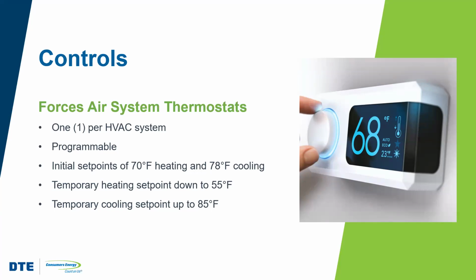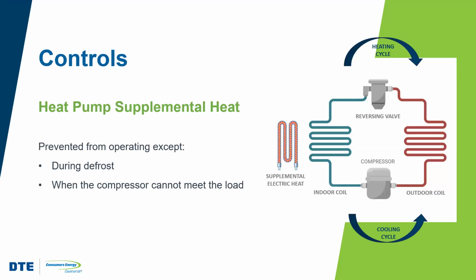The interior design conditions for a good design are 72 degrees Fahrenheit for heating and 75 degrees for cooling. But to encourage reduced energy use, the initial thermostat set points at turnover should be 70 degrees for heating and 78 degrees for cooling. And if the system includes a heat pump that has supplemental electric heat, the controls should ensure that that electric heat only comes on when the compressor system is not able to provide enough heat to meet the demand. And this can be located in the thermostat, or more than likely it's going to be integral to the heat pump itself. But either way, we want to be sure that we're only engaging electric heat when it's absolutely necessary.